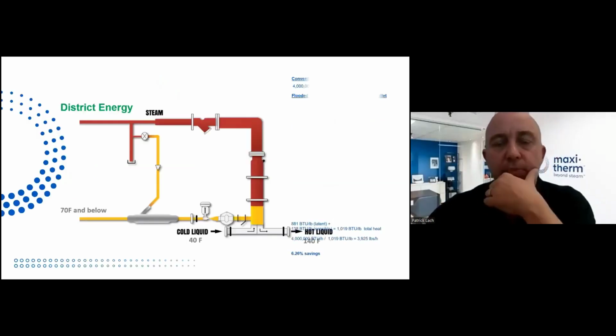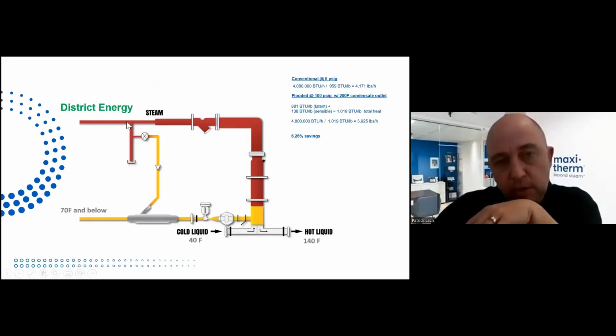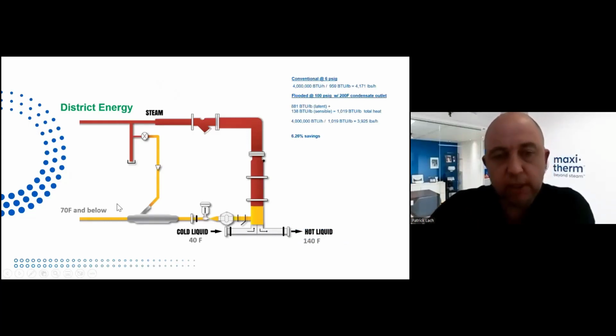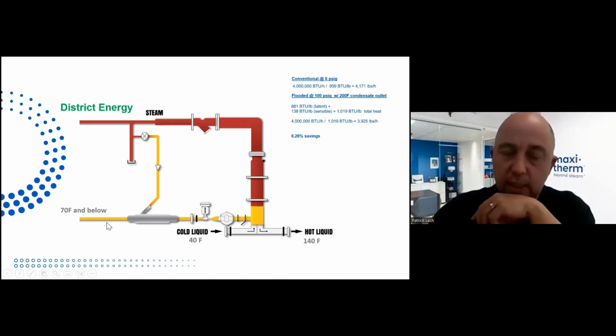On the district energy perspective, where the customer is buying steam, right? The number is greater, especially when they dump the condensate to drain, or there's no credit for the temperature coming back. But think also, if you have the condensing stack economizer, you can return cold condensate on domestic hot water. Return here is 40 Fahrenheit. We can oversize the heat exchanger, condensate leaving at 70 Fahrenheit.